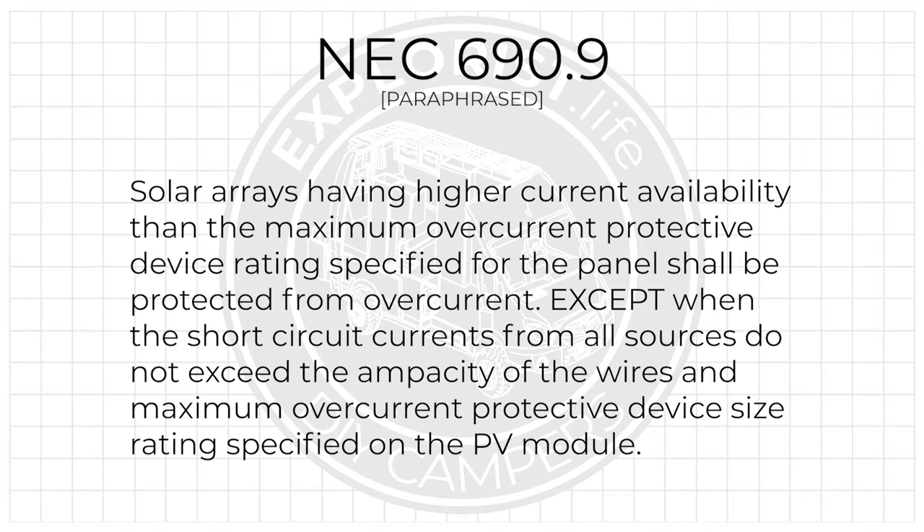Without wasting any more of your time, let's get to it. The National Electric Code is pretty straightforward on this issue. In NEC 690.9, paraphrased, it says: solar arrays having higher current availability than the maximum overcurrent protective device rating specified for the panel shall be protected from overcurrent, except when the short circuit currents from all sources do not exceed the ampacity of the wires and the maximum overcurrent protective device size rating specified on the PV module nameplate.